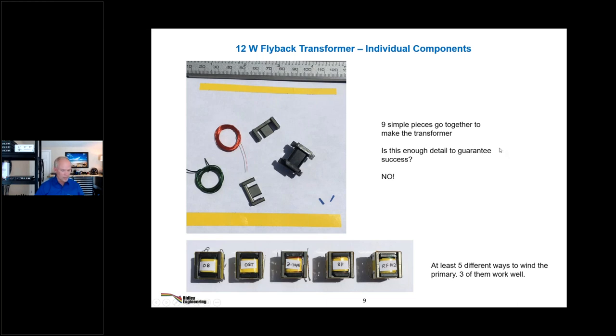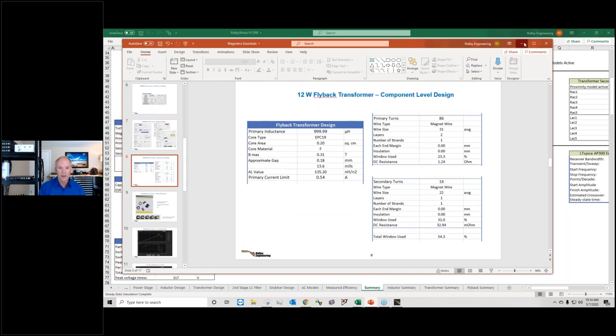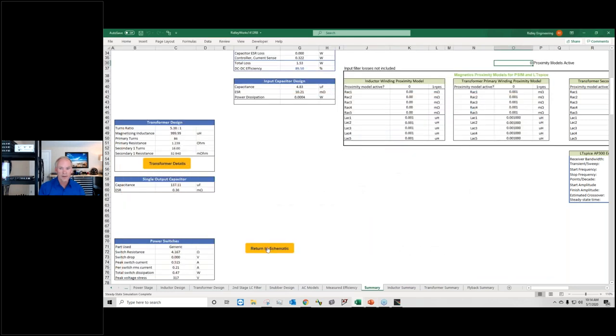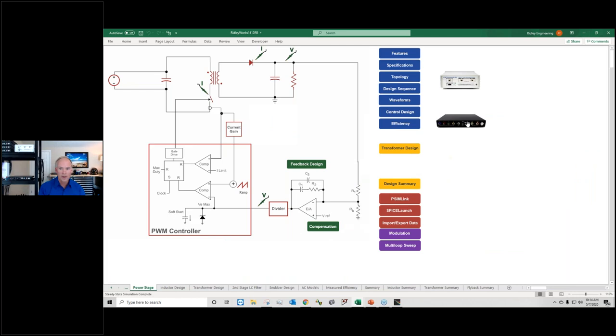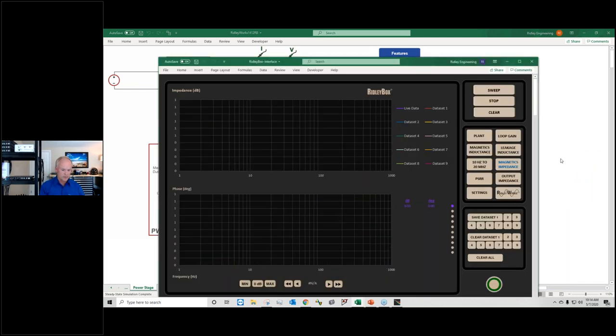So what do I mean by that? We're going to take one of these transformers, start with this first one, and define what I mean by working well here. We're going to close this down, go back to our design program, go to the frequency response analyzer, take the transformer with a couple of leads on the primary, and hook this up to measure it.